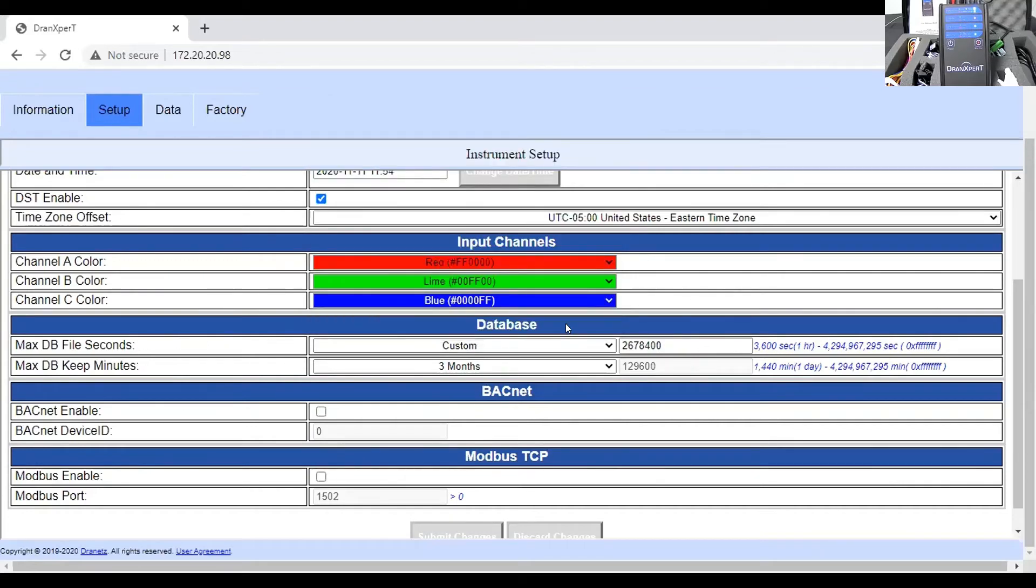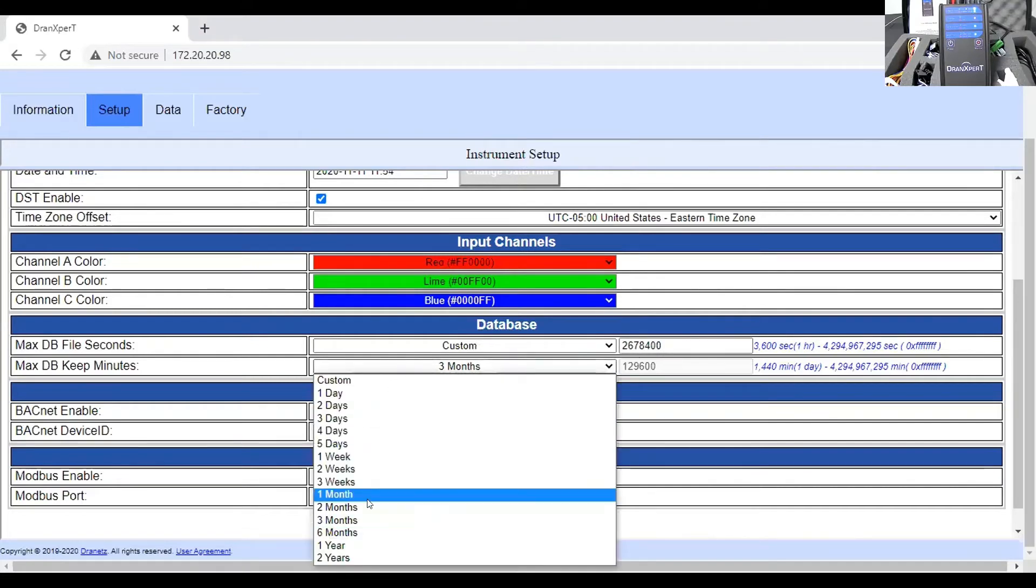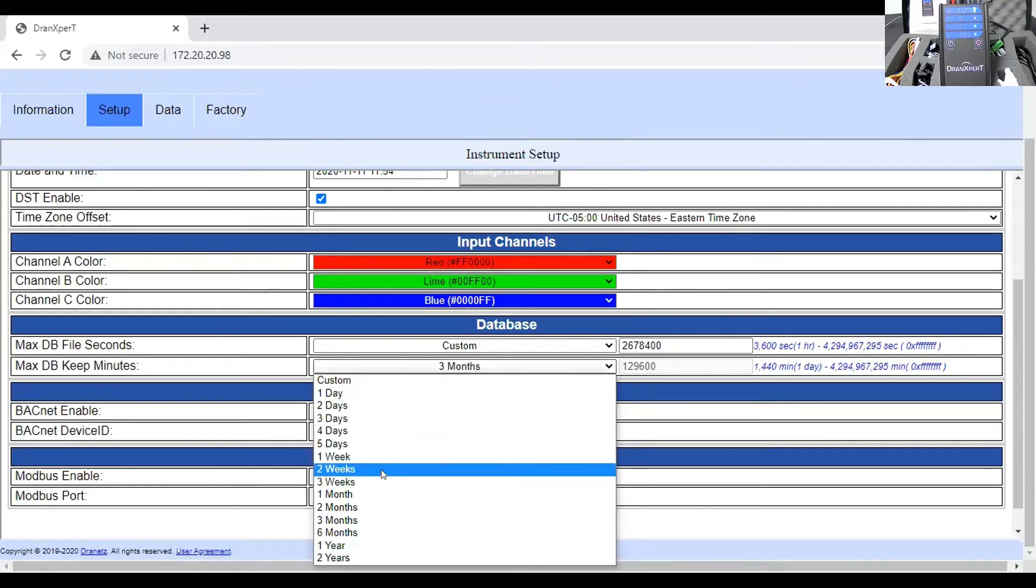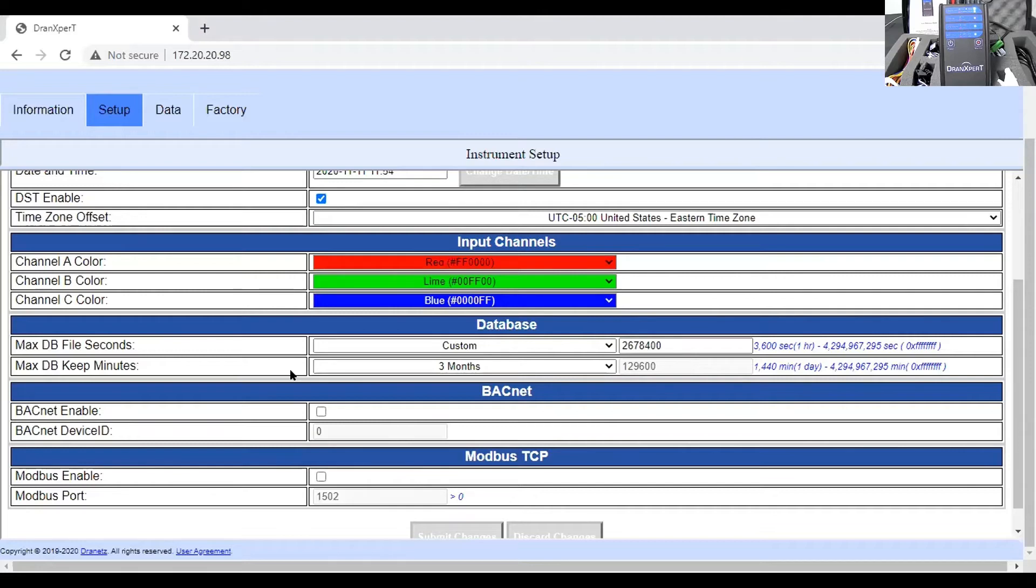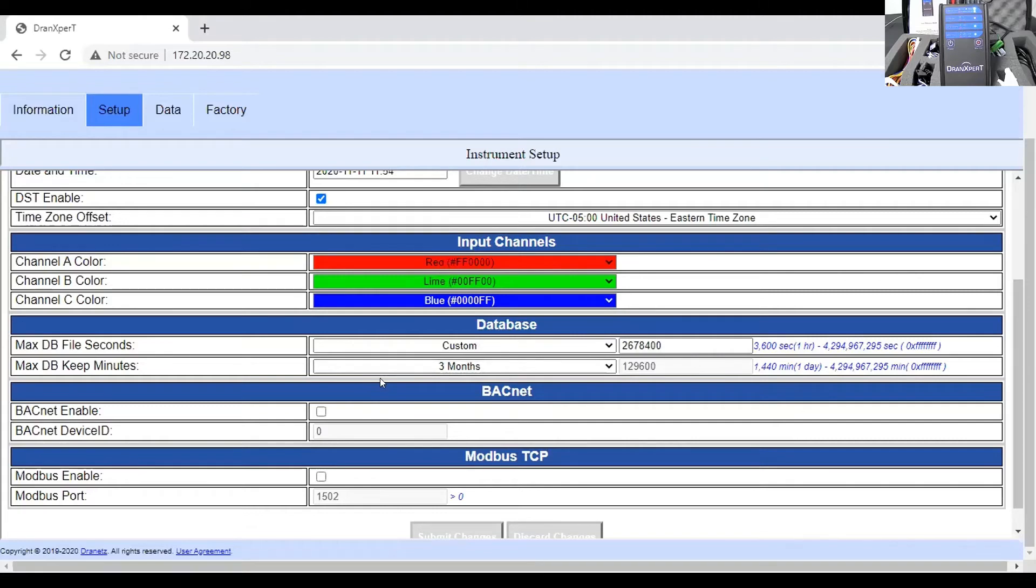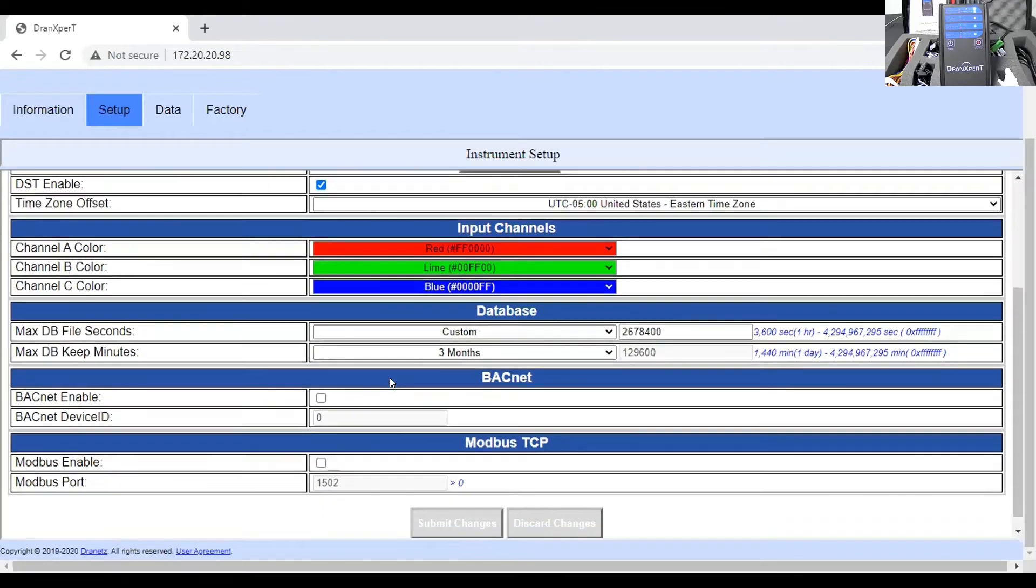Here, I can control how much information goes into the database, so to speak. So, the default in which it will record data before it begins a new data file is 31 days. But I can go to the drop down here and choose the capacity of a data file. You might have an application where maybe you only want to record for one hour. You're doing something specific. Maybe it's just one day, or maybe it's one year. So you have the option of selecting the drop downs here. And then, how long to keep the data files around. We typically use three months. But again, you have the option of selecting how long a data file is kept before it's purged.